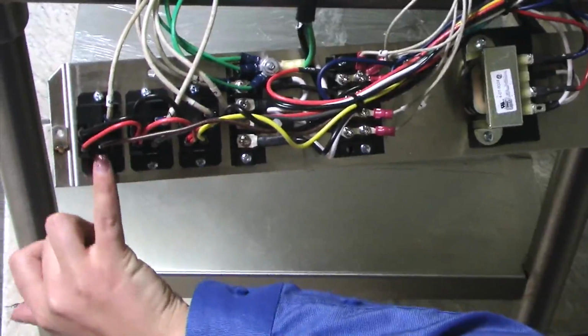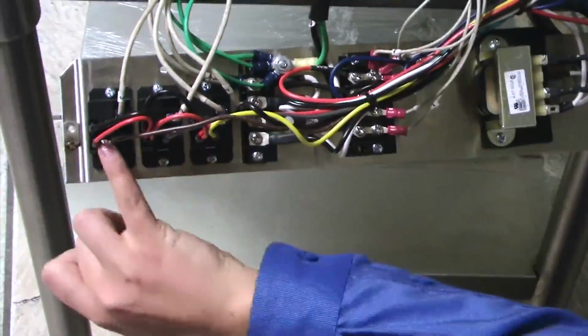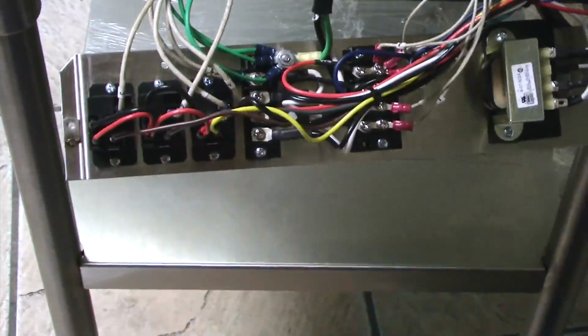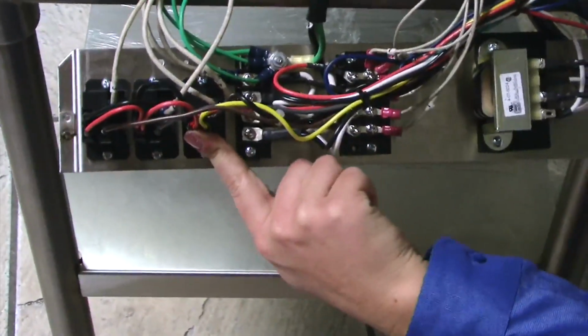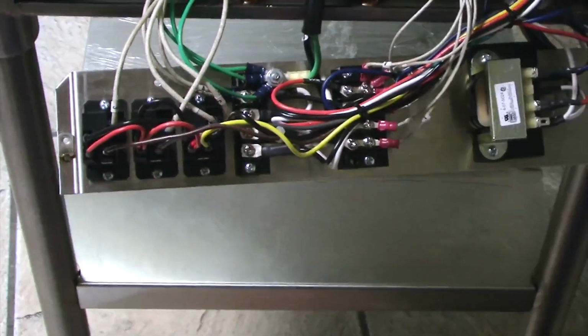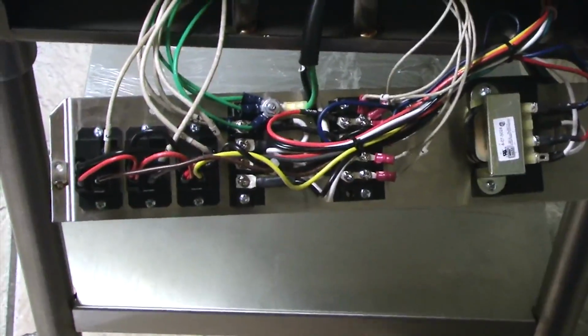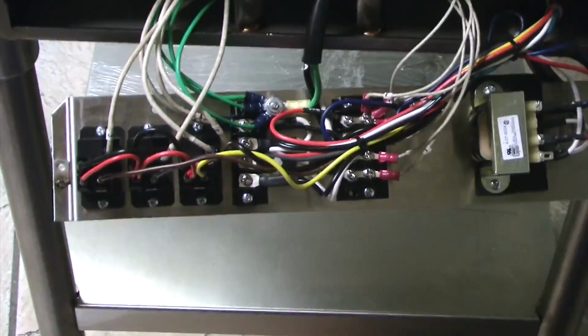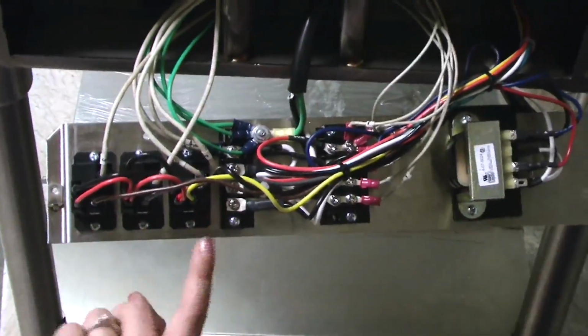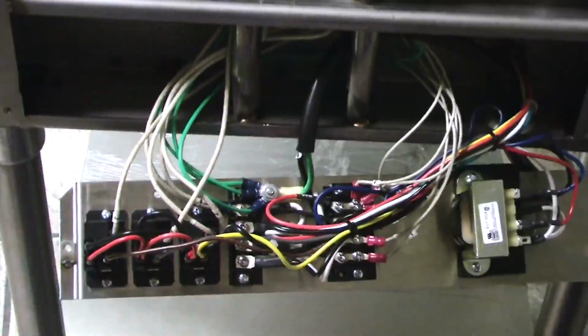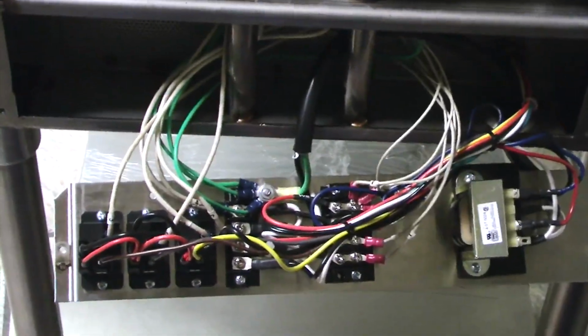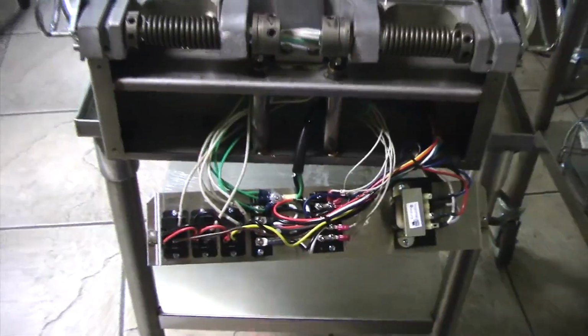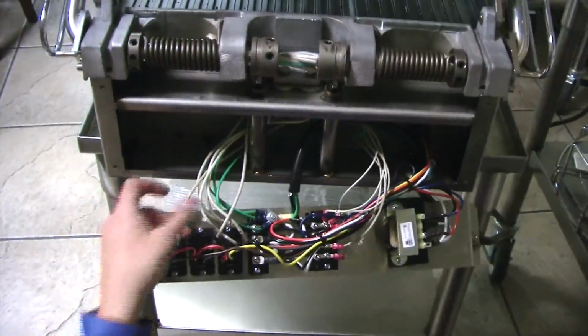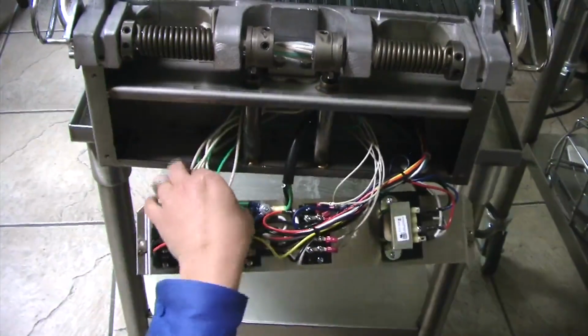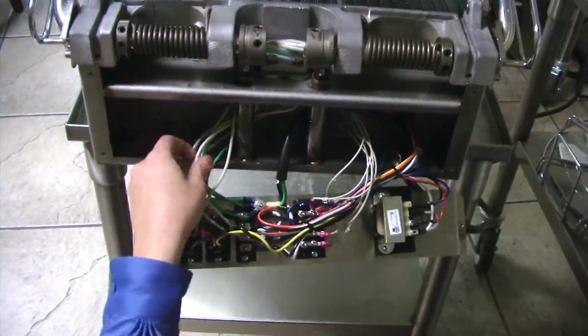Now if you disconnect the 3, the orange, the brown, the gray, and the yellow, and you're getting 12 volts here, 12 volts here, and 12 volts here, then you know your control is good. That's how you check your control. There's really no other way you can check your control except from these wires here. Now if you're getting 12 volt DC, 12 volt DC, 12 volt DC, and say this is not heating correctly, the zone 2 and zone 3, you know it's your relays because you are getting the 12 volts there. This will be 120 volts, outputting 120 volts. You got your heater wires.